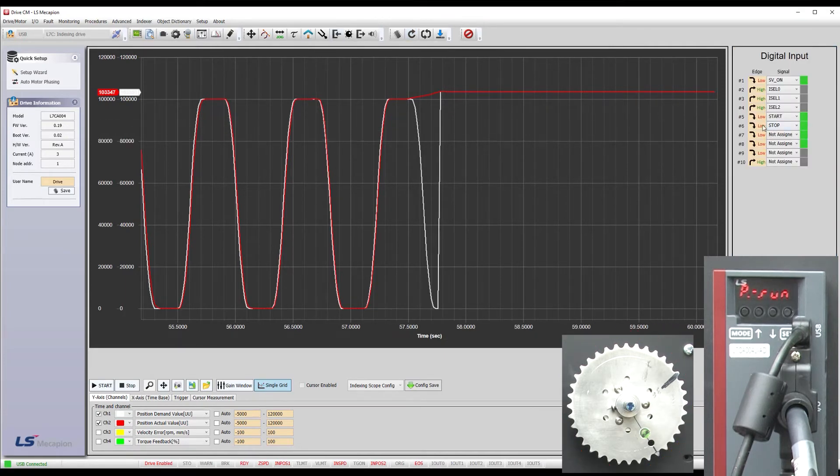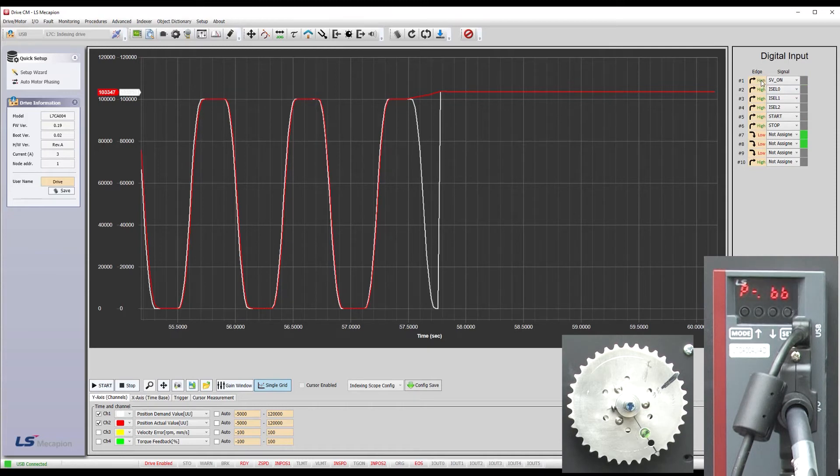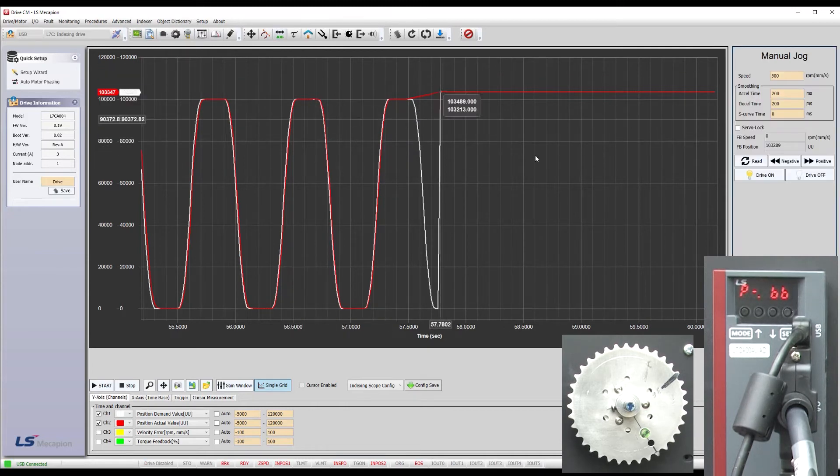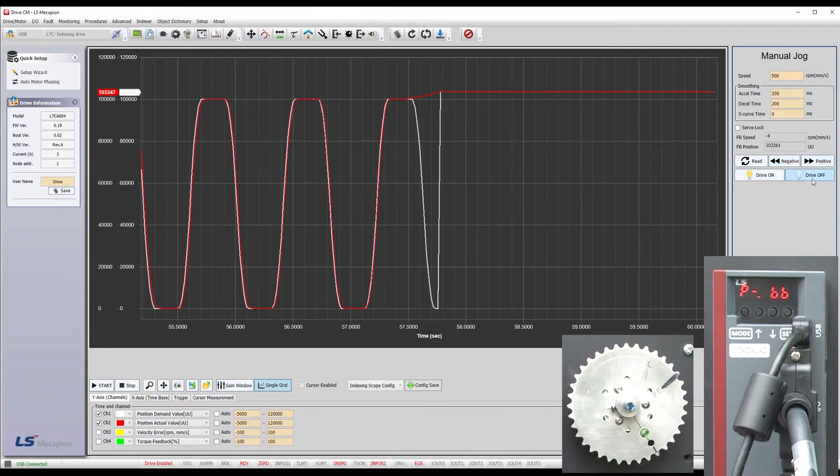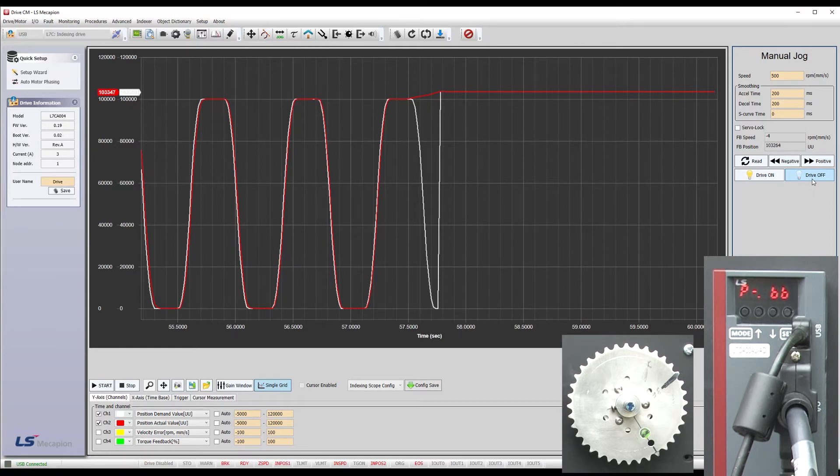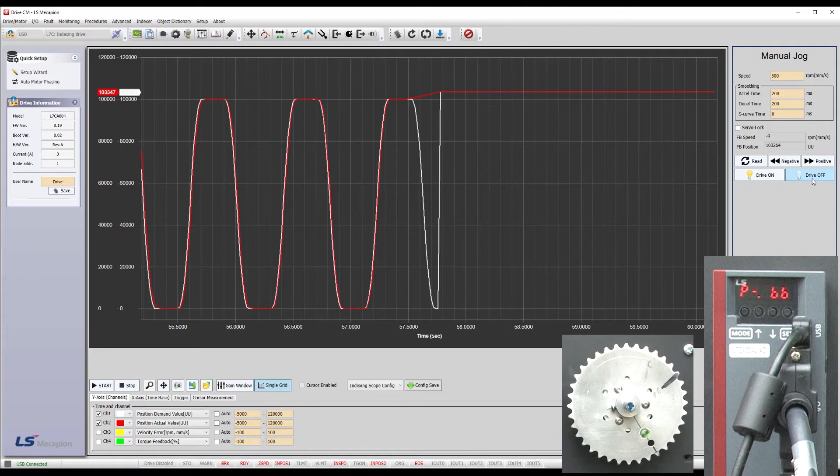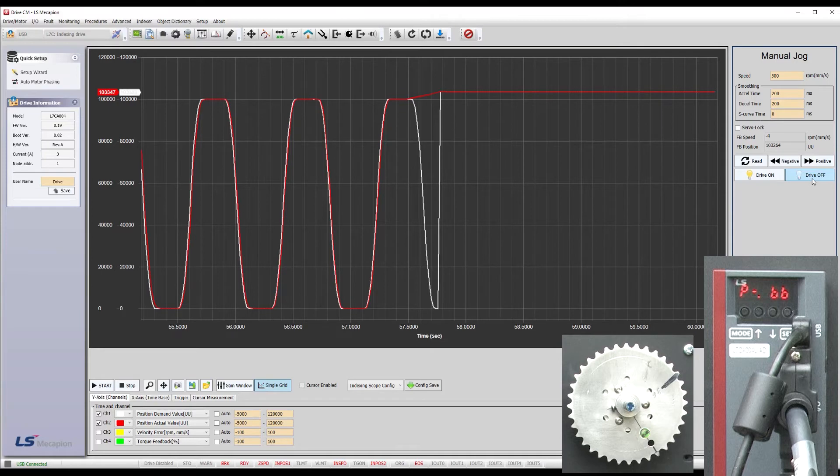Let's hit stop and then disable all the indexing controls. If I go to jog, enable the drive and try to jog the motor, hmmm, jog isn't moving the motor either. Why not? Well, I'm not exactly sure. But I think this free drive control software didn't reset everything it was supposed to so the drive is stuck. The drive thinks it's working, but there is no power being applied to the motor. There is some kind of output inhibit that didn't get reset.